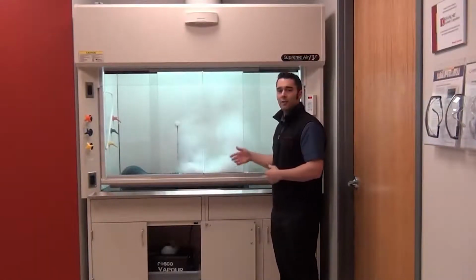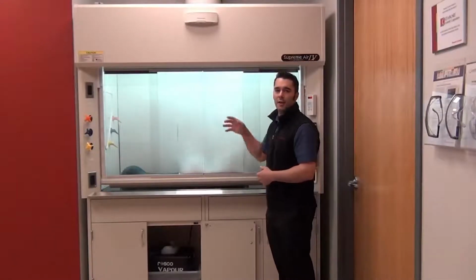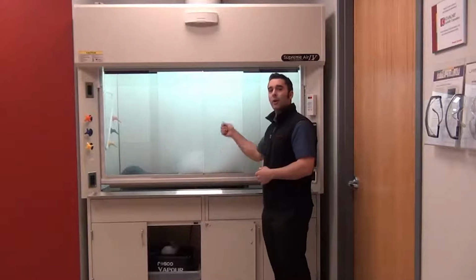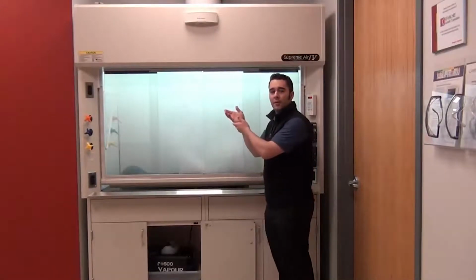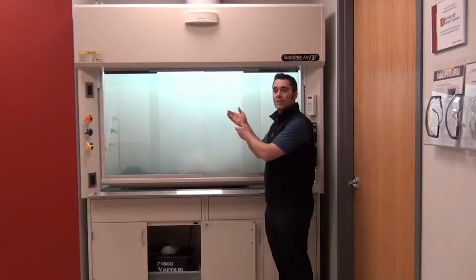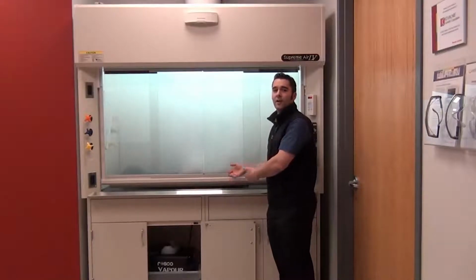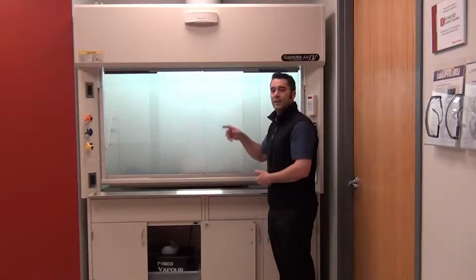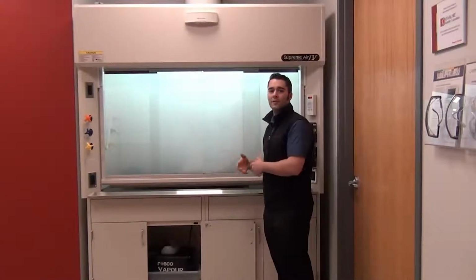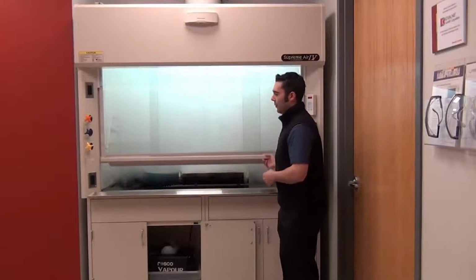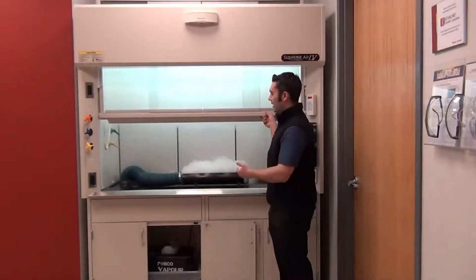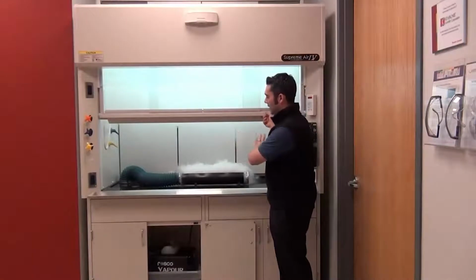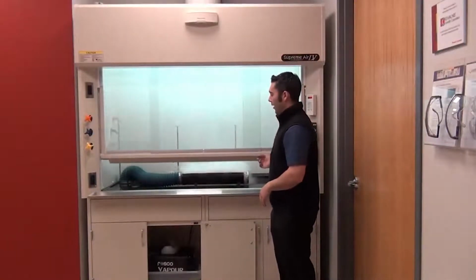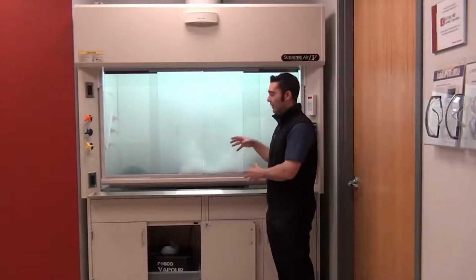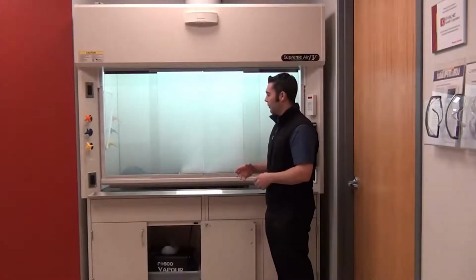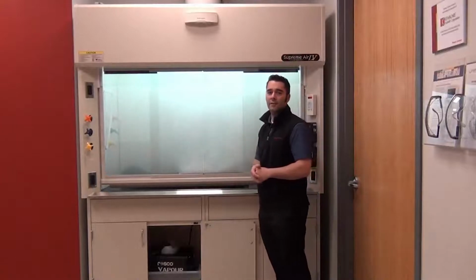The other thing you notice when I close this sash, you don't see extremely turbulent air inside of the fume hood, because just like when I open the sash, I need the face velocity to increase at the same rate that I'm moving the sash. When I close the sash, I need the face velocity to decrease at the same rate, guaranteeing that I don't have turbulent air which would knock things inside of the fume hood over. So again, as I open the sash, within 1 second my fume hood valve is where it needs to be, and you can see that everything is well contained inside of the hood. When I close the sash, you can see again that I have still good containment. Nothing gets out of the hood, but I also don't have very turbulent air inside of that fume hood.